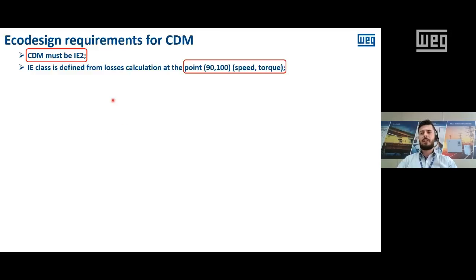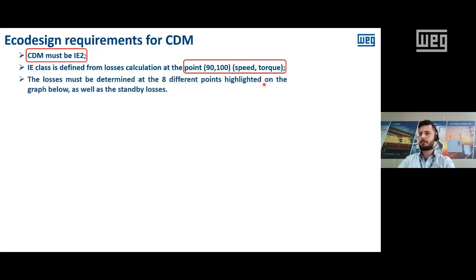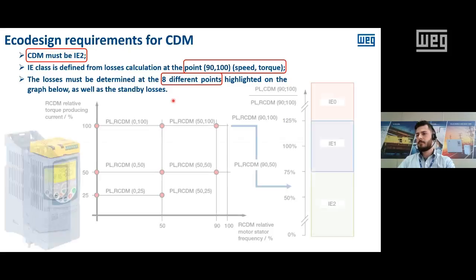How do you know if it's IE2 or not? So the IE class is defined from a losses calculation at the point of 90-100, which is 90% speed and 100% torque. But the losses must be determined at 8 different points, which will be highlighted here in the graph, as well as the standby losses of the product.